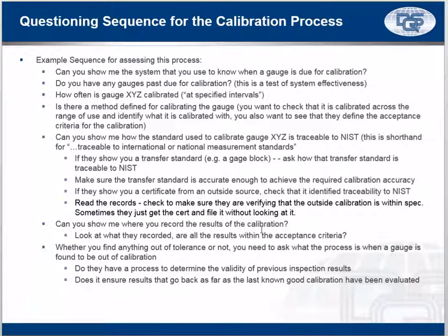So you want to look at the results. You want to see if the results are recorded and whether there are any acceptance criteria and whether things were within the acceptance criteria. Whether in your sample you find anything out of tolerance or not, you need to ask what the process is when a gauge is found out of calibration.